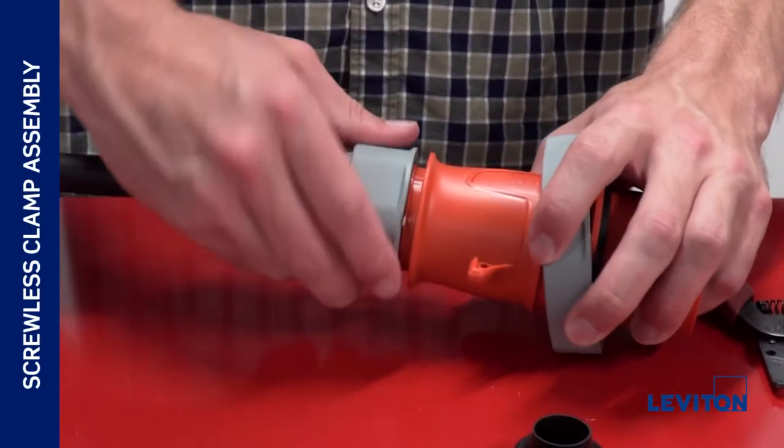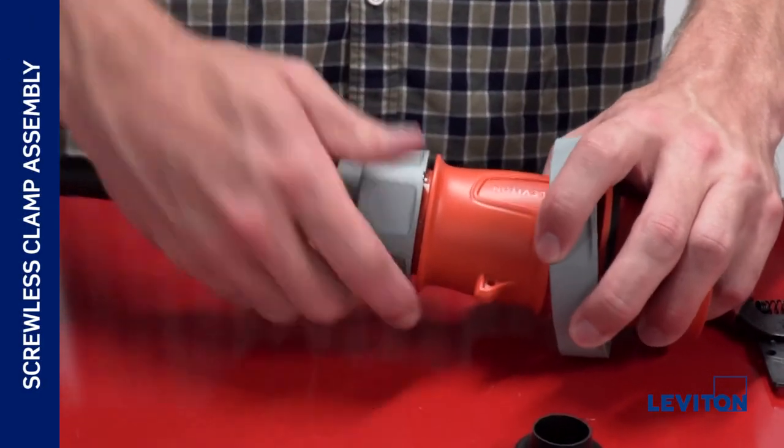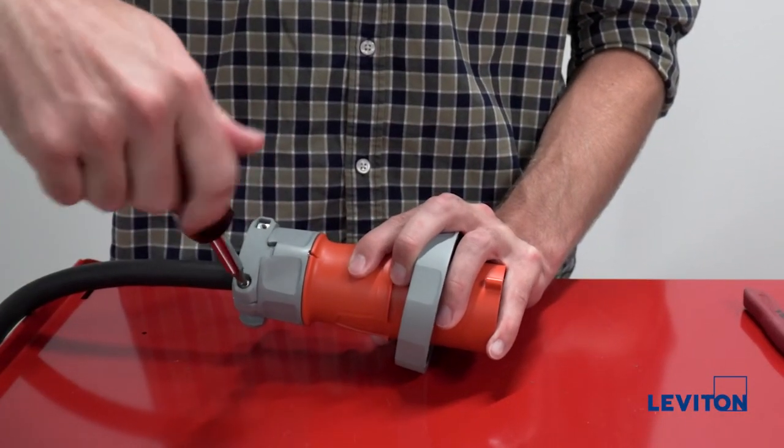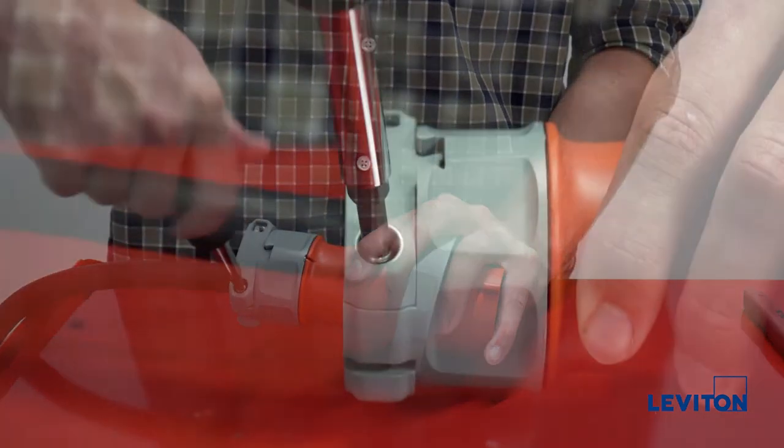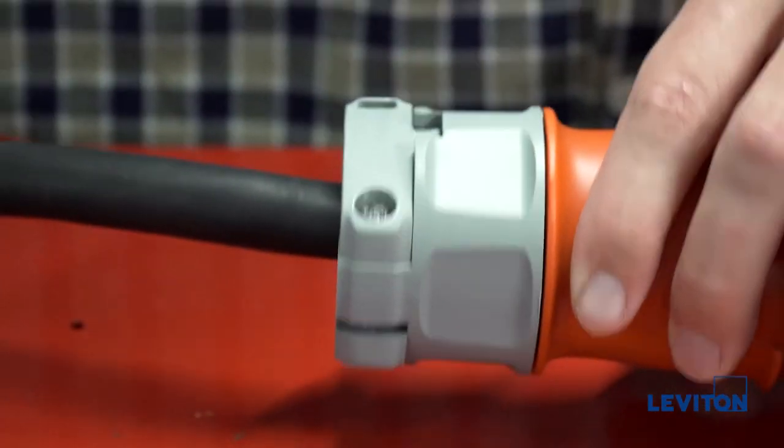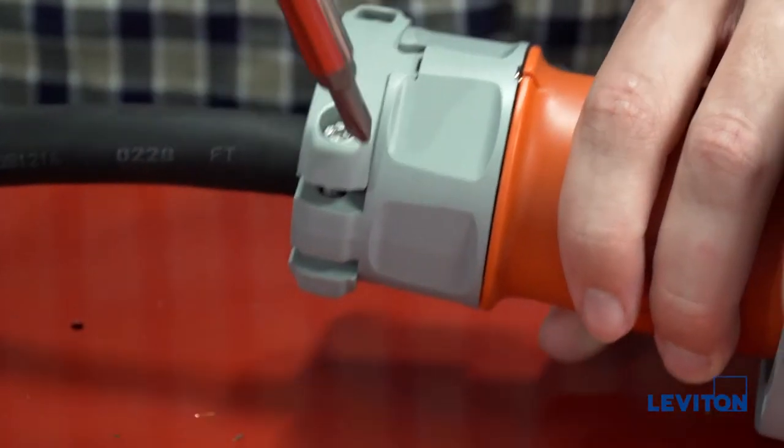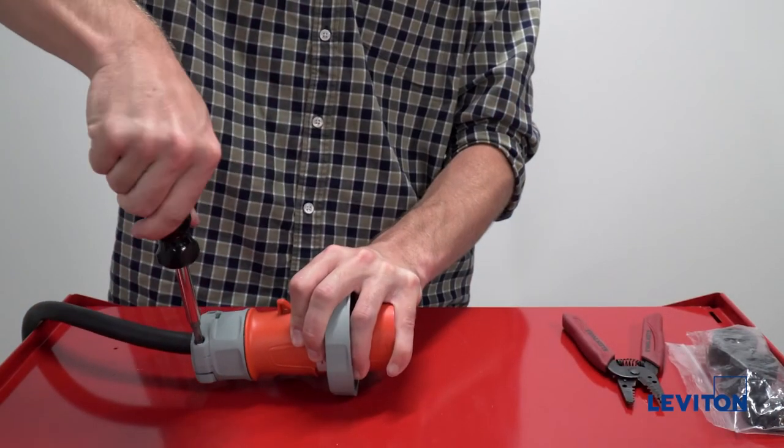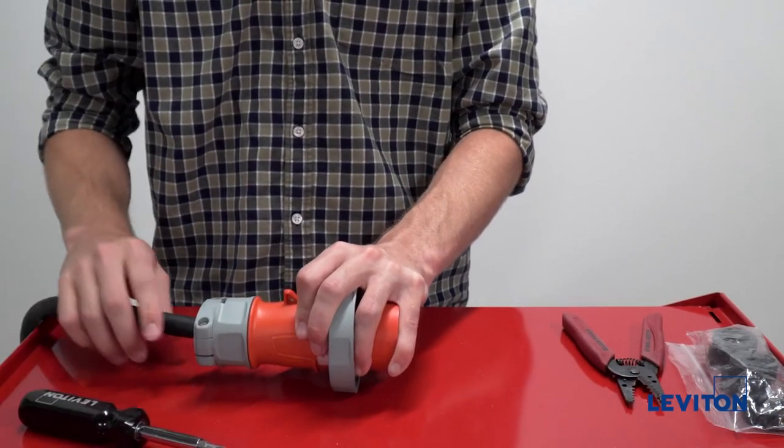If you are installing a device with a screwless clamp assembly, your installation is now complete. If you are installing a device with a standard saddle clamp assembly, use your screwdriver to tighten the clamp screws to 10 inch pounds. Again, do not over torque. The installation of your plug or connector is now complete.